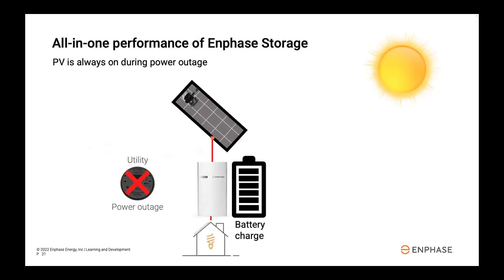All battery storage systems must have the ability to curtail the power of the solar PV system in some way during a power outage. If the battery is full and the home is using very little power, the power from the PV system essentially has nowhere to go, which would cause the battery system to shut down.